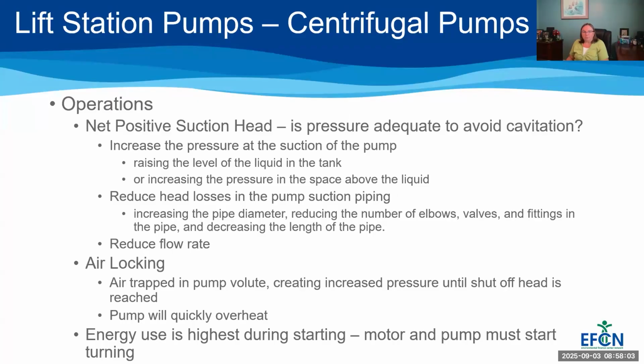The operations of the pump, the net positive suction head, this is another term you should be familiar with. Is your pressure adequate to avoid cavitation? That's what we're talking about. It's the difference in the increase and the influent and effluent pressures. And one way to avoid your net positive suction head being a problem is reducing your flow rate. Air locking, if you get air trapped in your pump, that can be a problem. Also, it's important to note that energy use is the highest during your pump starting because you're using energy to get everything moving. It's like, me as an old lady trying to get out of bed in the morning, it takes more energy than once I'm up and going, right? So you've got to have more energy to get the pump going than any other time.